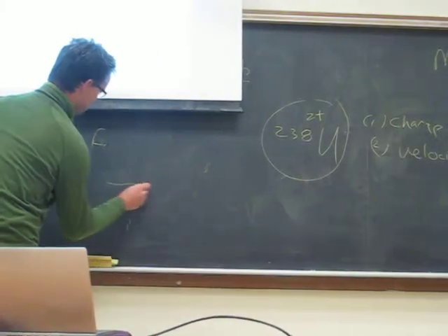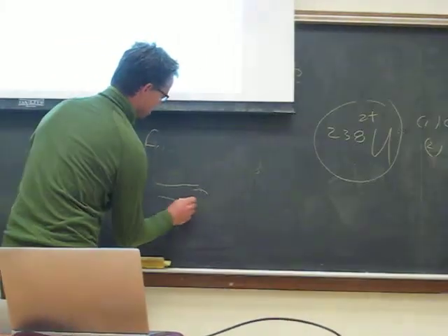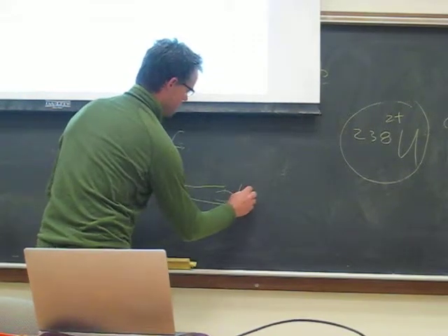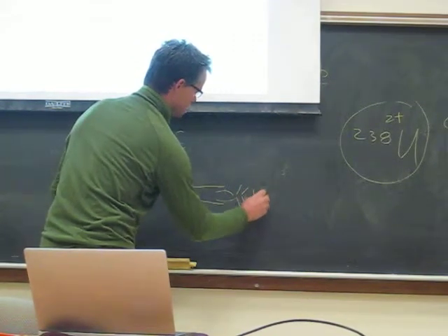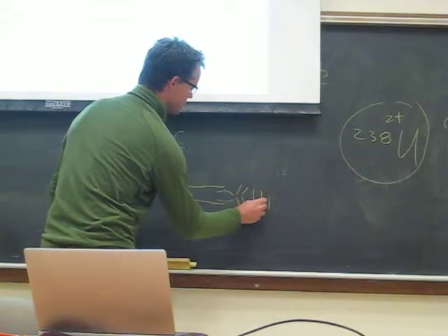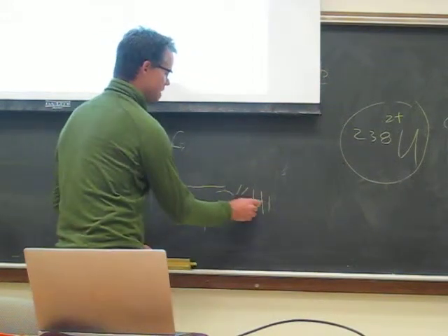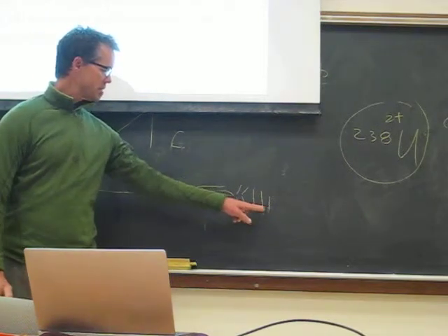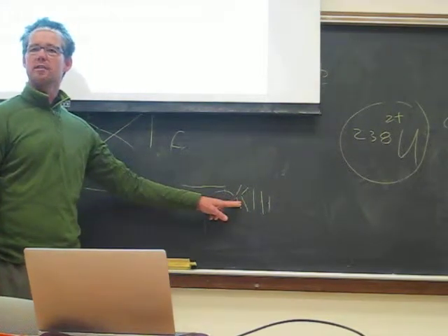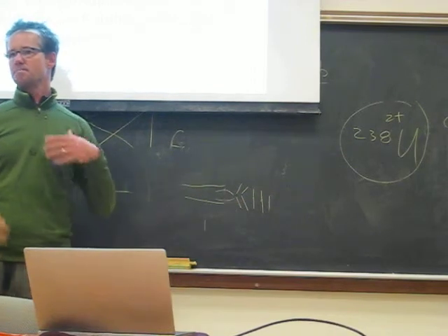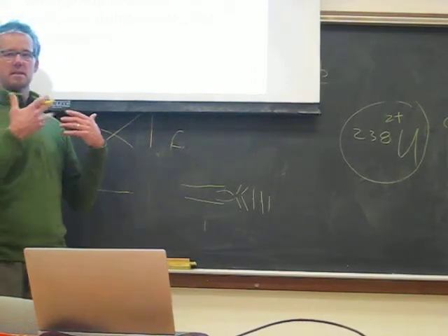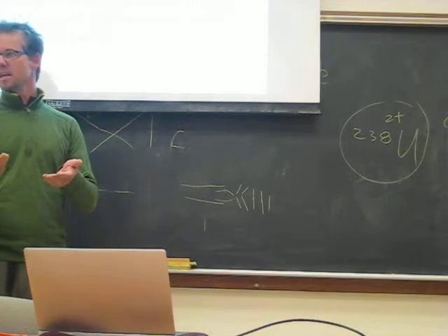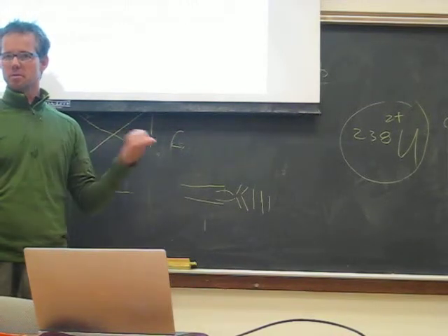If I were to have a torch coming like this, and here's the cone of the torch coming out, right here at the end of that torch are a series of plates. And these all have little slits in them. And these all have different electrical potentials applied to them. And the potential applied here is greater than the potential applied here, so that the ion is charged, and you have to set a mass spectrometer up to either accept and accelerate cations, positive ions, or negative ions, right? Because you can't do both at the same time, obviously, because they'll go in different ways, right?